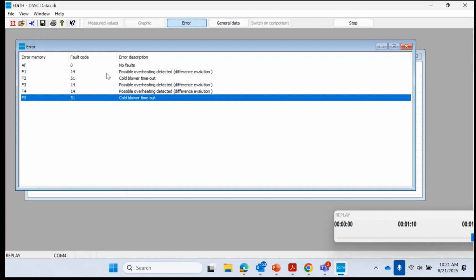Now, if you did have a lockout code, you would click on the delete button that will appear over here when you do a live test, and that will clear out the codes. So in the case of a first generation heater, if you do have an ECU lockout, you have to clear the codes by simply clicking the delete button, and that way you can unlock the ECU. Now remember, unlocking the ECU does not fix the problem. Unlocking the ECU only allows you to test run the heater again, but you have to find out the root cause of the failure and fix it. Otherwise, the heater will fail again repeatedly and eventually lock out again.